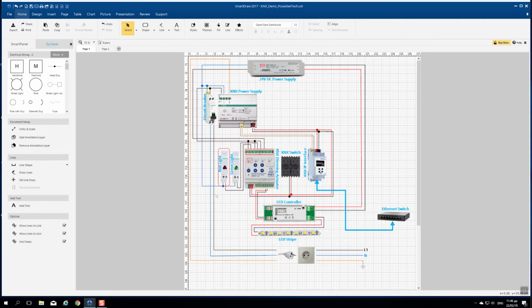So, in channel A of this actuator, we will connect line from circuit breaker and the red light. Of course, red light, in order to operate, will need also the neutral from the circuit breaker. Channel B, like channel A, will follow the same connection in order to control green light. And channel C will be used to control the AC power is needed from the 24 volts DC power supply of the LED stripe. Power supply will take the neutral from circuit breaker.